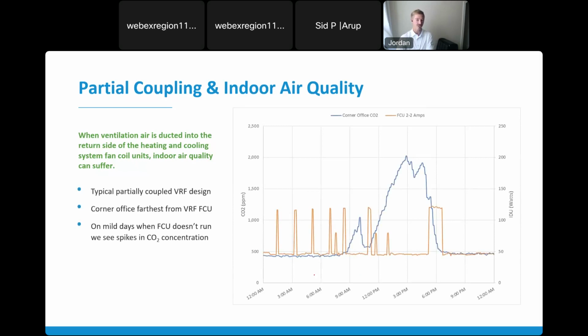This is a typical office building with a partially coupled design. So VRF fan coil units are the primary heating and cooling system. When the ventilation air is delivered on the return side, this works fine when there's an active call for heating or cooling. This is the fan coil unit power. So it's cold in the morning, the fan coil unit is cycling on, and CO2 remains low in the space.